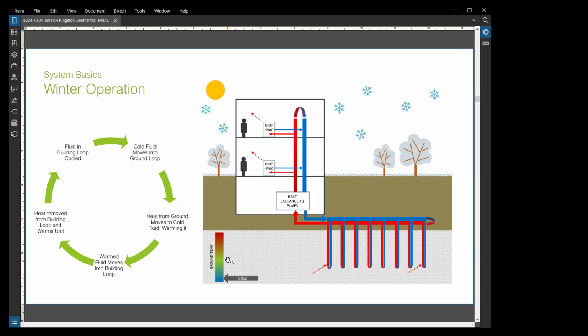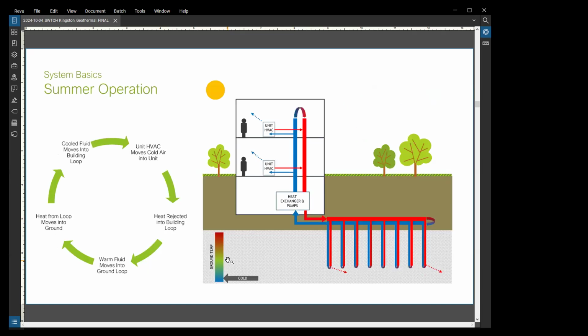That's why it's really important to make sure that we balance the geothermal system so that whatever heat you've extracted from the ground in the winter, you're putting back in the summertime. And so in the summertime, the operation is essentially flipped. We think of air conditioning as blowing cold air into a space, but maybe more accurately, what we're actually doing is taking heat out of the space. We're not blowing cold, we're taking heat out of the space. And so when we take the heat out of the space, we're putting it into that liquid, because it's basically going in the reverse path of what it did initially.